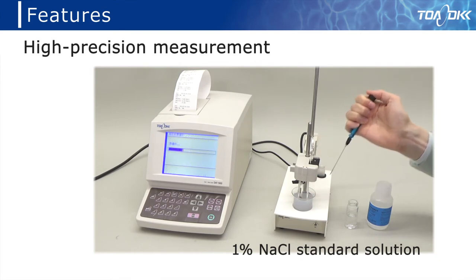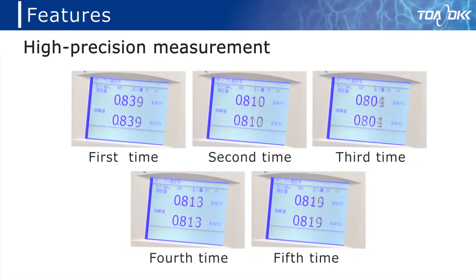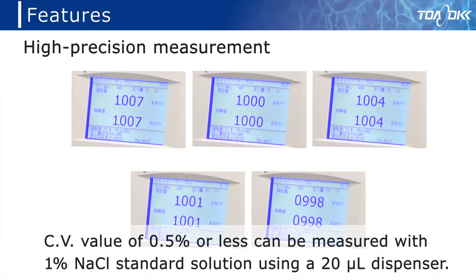The third feature is high precision measurement. Here is an example of measuring 1% NaCl standard solution. The video shows five consecutive measurements. It is possible to achieve a CV value of 0.5% or less with 1% NaCl standard solution using a 20µL dispenser.